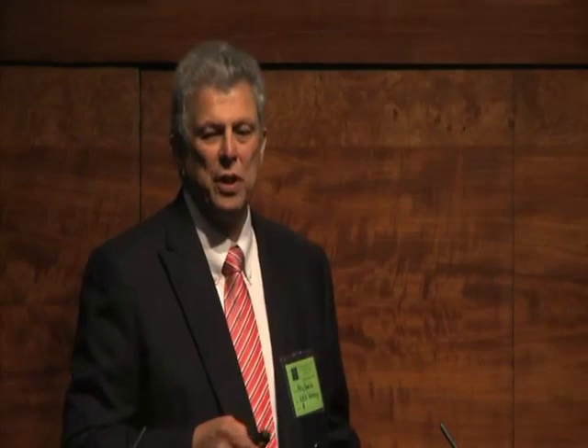It seems simple, but the technology is much more complex. What happens is the interaction between the in-situ forces here and the pressure that you put in. You need to know how to maneuver this. A unit like this, for instance, if you go to 5 kilometers, you will get about 150 to 200 degrees, and it produces around 4 to 8 megawatts electric. But with it there is also a lot of thermal energy. In the past, when I first started, the discussion was that all we want is electricity, not heat. But the equation has changed altogether because the heating cost has gone up, so thermal resource is equally important.